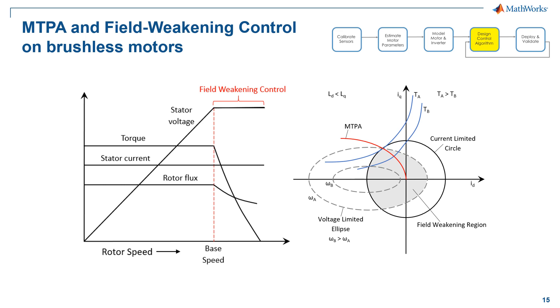We manipulate the D-axis stator current to be a negative value, which means we reduce the field current so that the applied stator magnetic field is in the opposite direction to the rotor magnetic field. As a result, the net magnetic field is reduced, the back-EMF is reduced, and so is the rotor flux linkage, which allows the motor to run above the base speed.